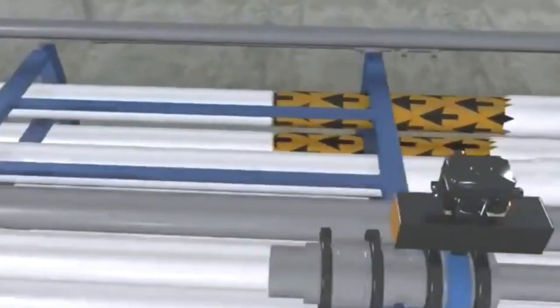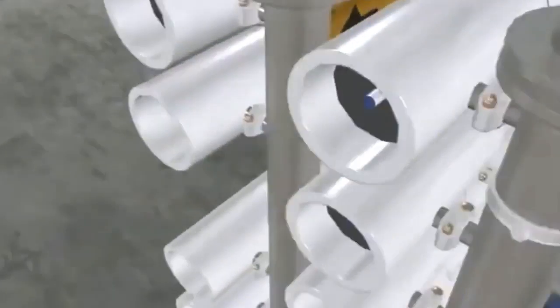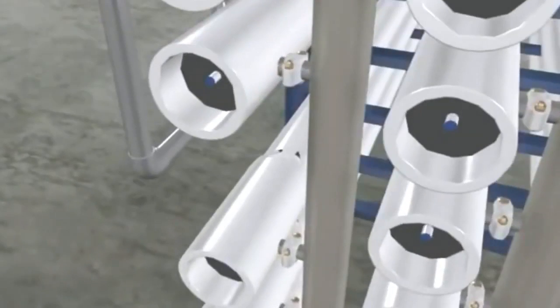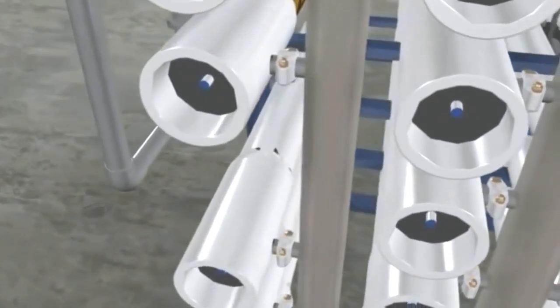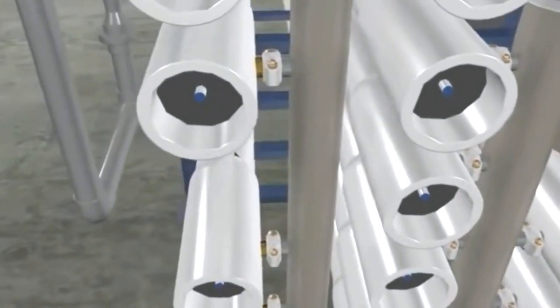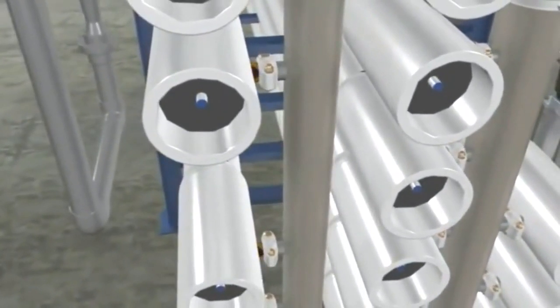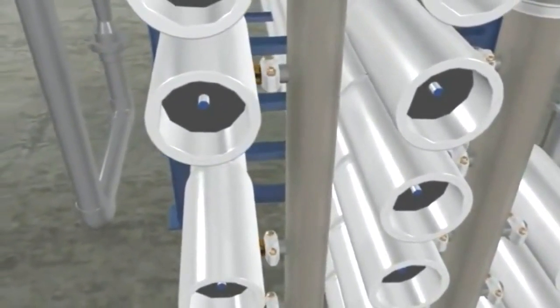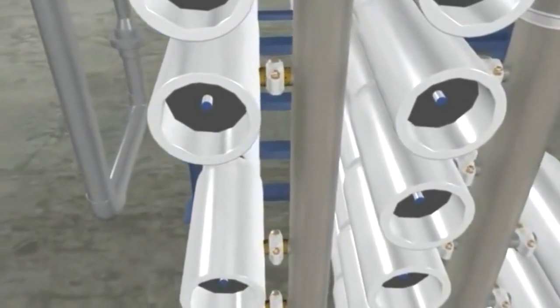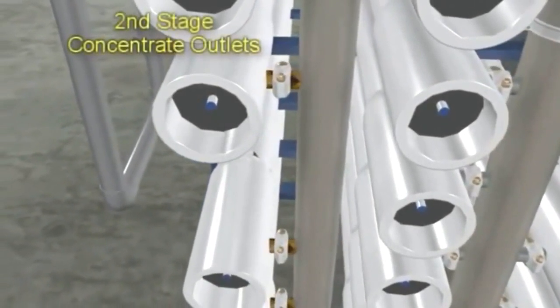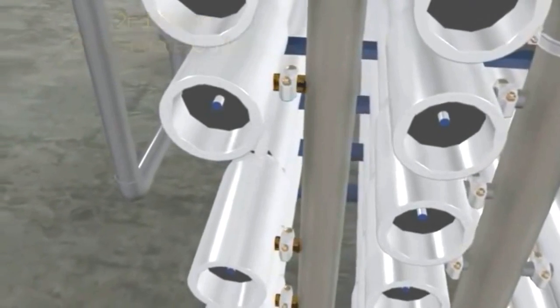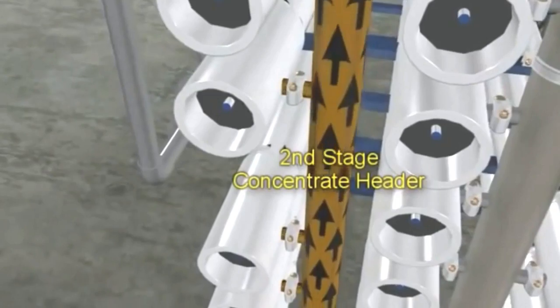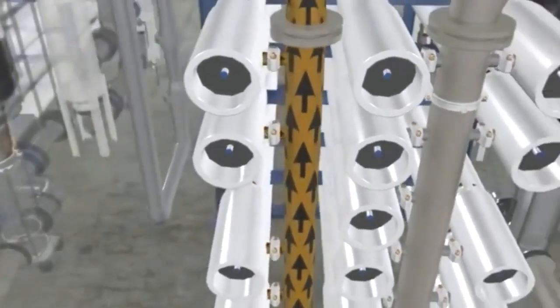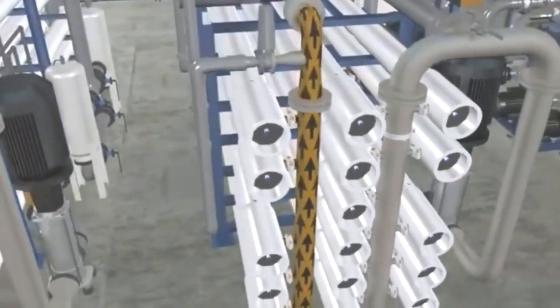As with the first stage pressure vessels, there are two exiting flow paths from each second stage pressure vessel. The flow path, which exits the side of each second stage pressure vessel, is part of the second stage concentrate outlet flow. This flow path consists of the concentrated reject water from the first stage of the RO, which was further concentrated in the second stage of the RO. Second stage concentrate flow is the final reject flow of the RO system when it is in operation.